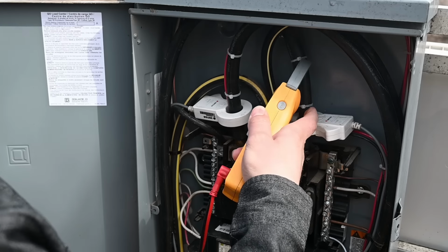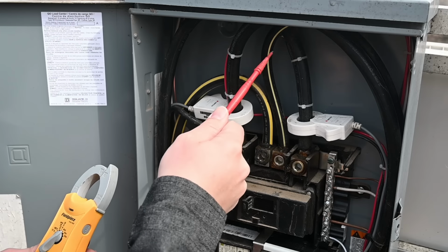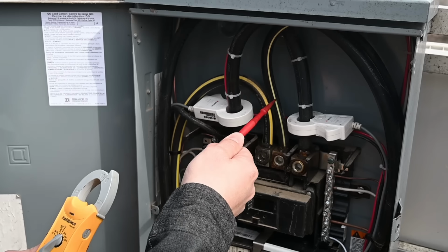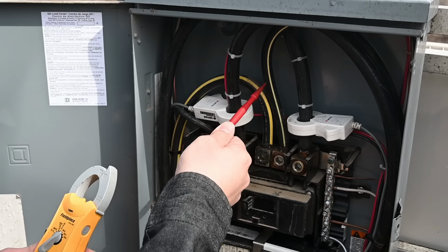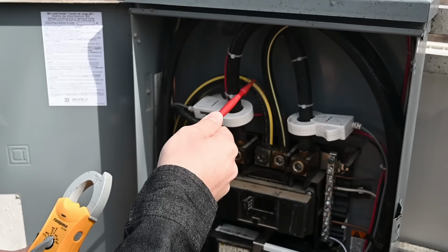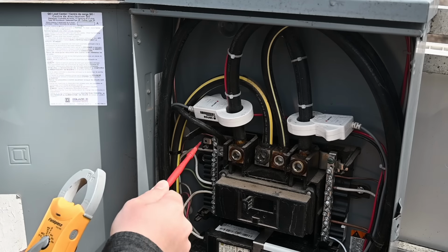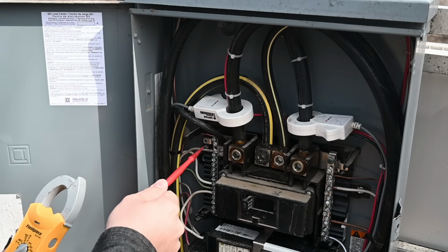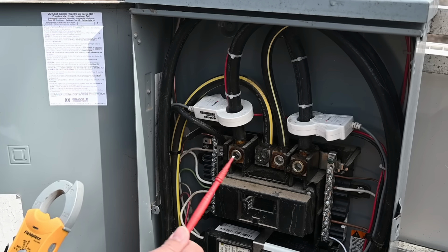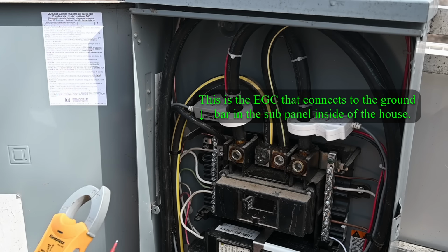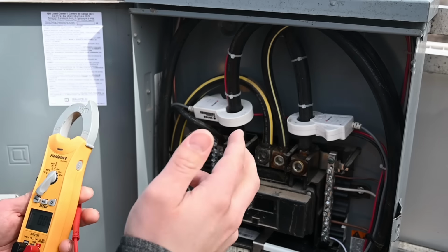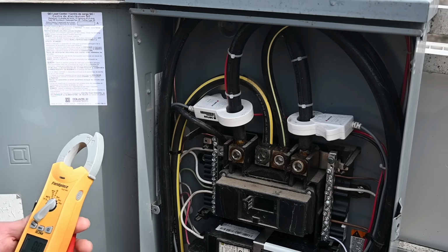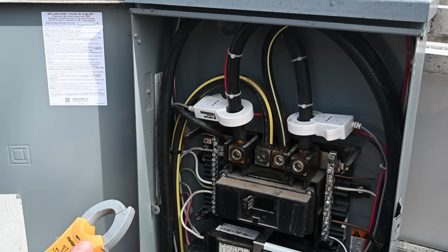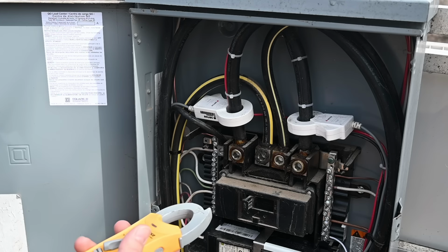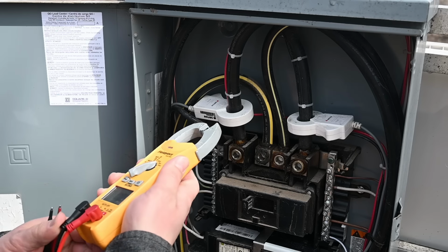Now I wonder if we have any current flowing on this neutral wire, which would be coming from the center tap of the transformer. It comes in and ties to the neutral bus, which is tied to our grounding system. Down here is where our grounding electrode ties into this neutral bus. So if we had current leaking to ground, it could maybe be coming from that center tap of the transformer. I don't know, we're going to find out.